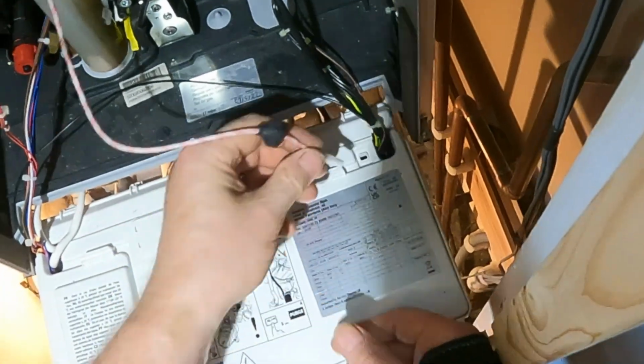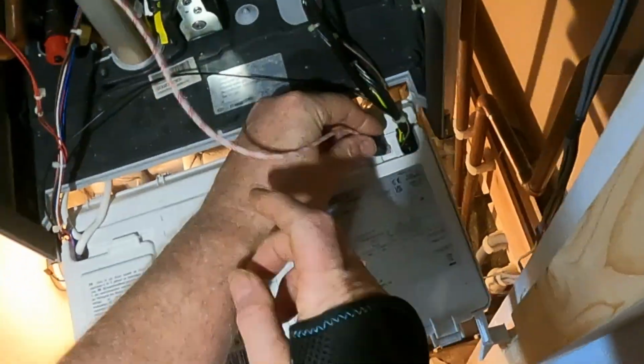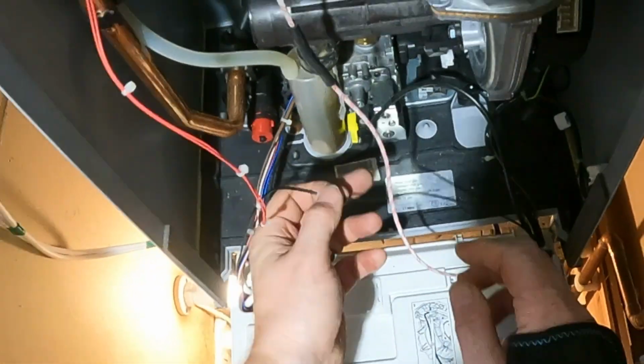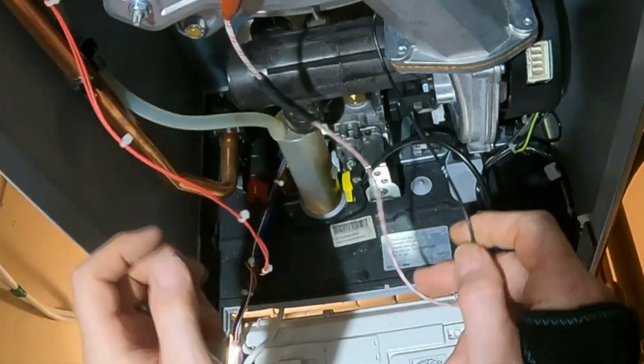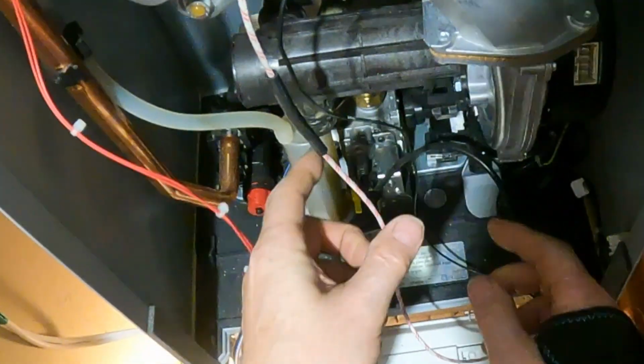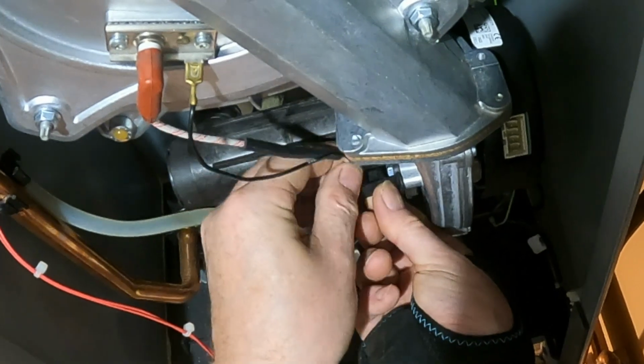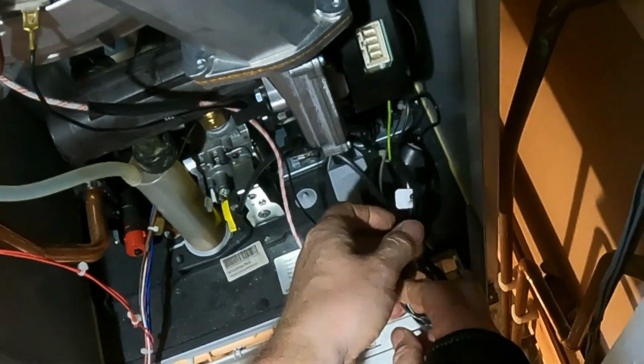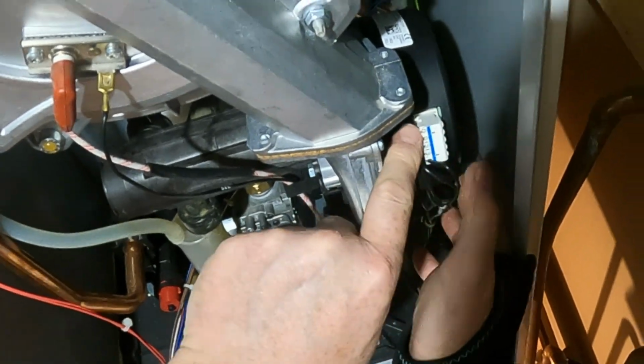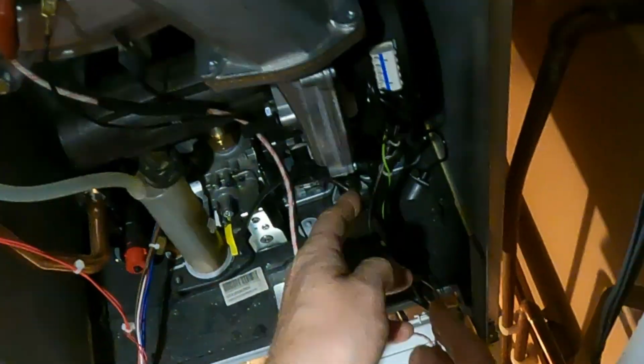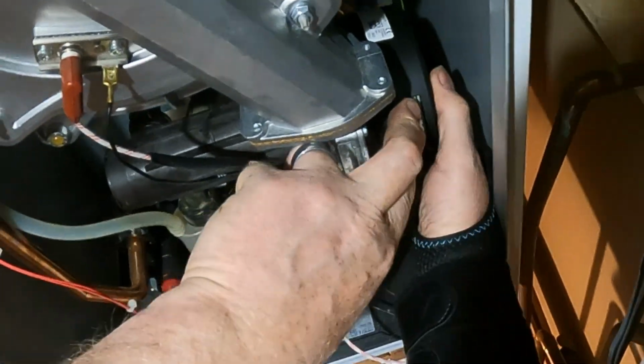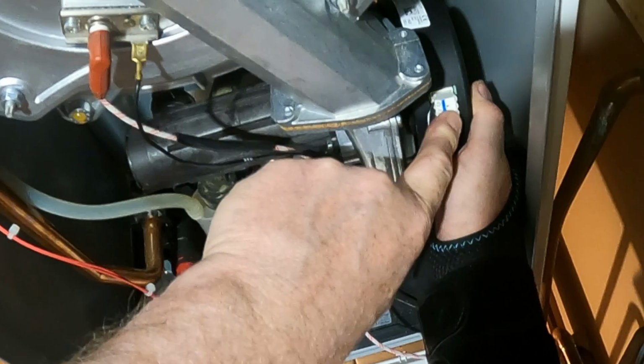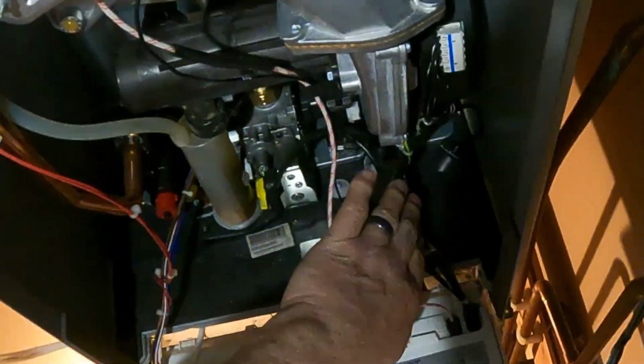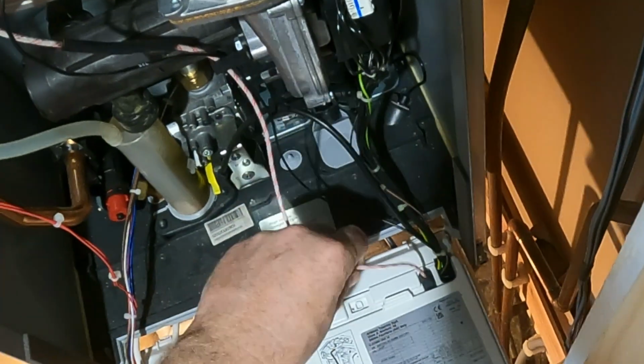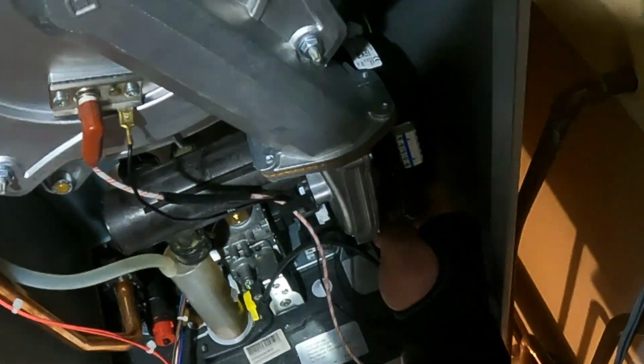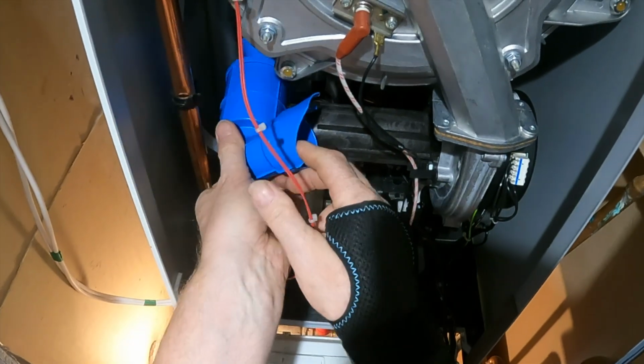We can now put our probe back and the cover with our ignition lead, and don't forget the earth wire. And put it back in the little clip, and then the wire for the fan. Now, one of the things I have learnt about this boiler, having so many at the centre, is when you put the fan wire back in, just make sure that that cable isn't touching the side, because if it does, it makes a vibrating noise. Anyway, now we can get the silencer back on.